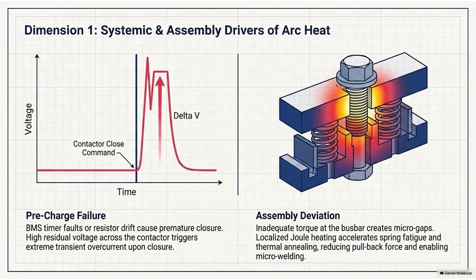It really is. The spring becomes sluggish. It loses the aggressive mechanical snap required to pull the heavy contacts apart faster than the arc can form. So when the driver turns the car off and the command comes to open, the contacts pull away lazily. That slow, hesitant separation allows a miniature DC arc to form and sustain itself just a fraction of a millisecond longer than it should. Just long enough to do damage. Yes. This creates tiny, microscopic welds on the silver surface. Over time, these micro welds accumulate, creating a sticky friction, until one day, the severely weakened spring simply lacks the physical force to break the micro weld. The contactor remains permanently stuck.